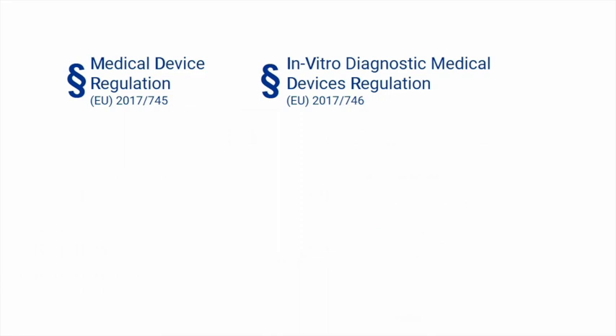What are the key points of the EU MDR? The regulation is now extended to scope cosmetic and aesthetic devices too. Stringent requirements for compliance for manufacturers to ensure patient safety. There must be a national registry where all manufacturers have to register themselves, and a database where the devices they put on the market must be registered in a detailed manner to guarantee traceability through unique device identification, also called UDI.